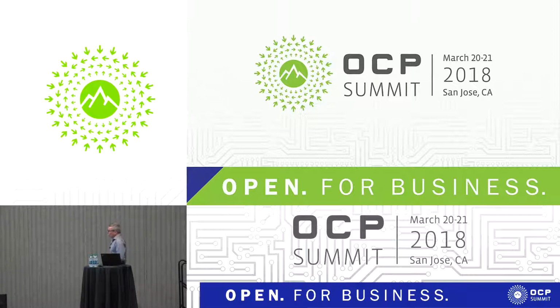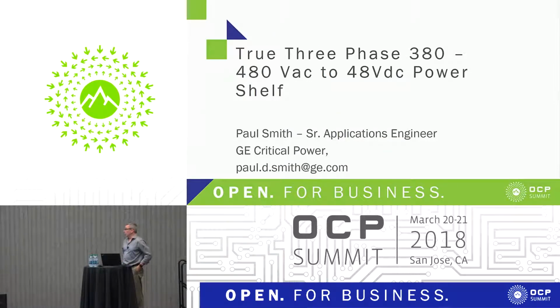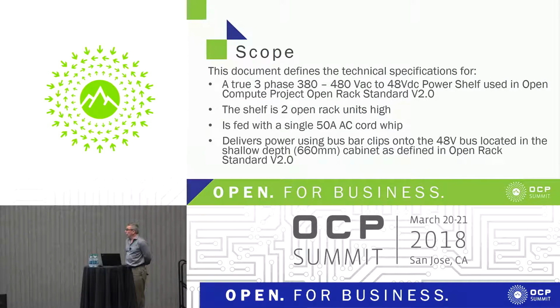We're going to talk this morning about an application for OCP in the data center, for OCP rack powering. Our particular slant on this is a proposal that we've put together for a contribution, and it's going to look at a true three-phase, and the input range will be from 380 to 480 volts, plus or minus a bit, and give you a 48-volt DC output. It will give you a full 24 kilowatts. That's 4 modules, 4 6-kilowatt modules. So depending on whether you want to provision with N+1 redundancy, you can call it 24 or you can call it 18 kilowatts in total.